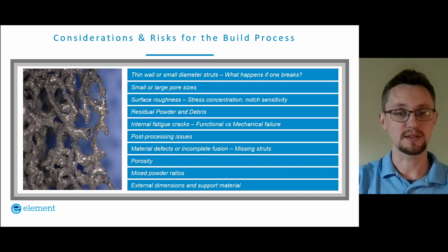As you're running your testing in a matrix, it can be really difficult to find cracks internally. So how do you do that? Can you do it via CT? Do you cross-section it? Do you set displacement criteria? Is it functional? Is it mechanical failure? You want to look at post-processing issues, so issues related to HIPping or heat treating. Material defects or incomplete fusion is another important area. I've seen lots of parts come to us that are essentially missing struts, so either they broke off or there was incomplete fusion. And that's really critical for the performance of that device.